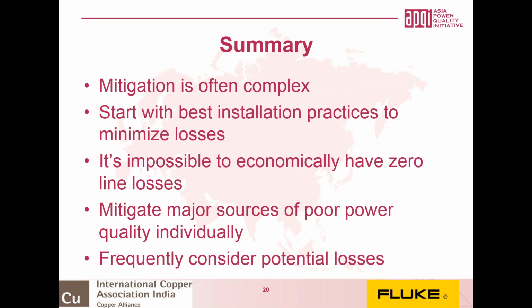Last things are, mitigation is often complex, and first of all, you're best starting with best installation practices to minimize losses. If you size your conductors correctly and you balance your loads properly, then you have a much stronger opportunity to come up with an efficient electrical system. It's impossible to have zero line losses. You have to accept that there will always be some line losses. But one of the things is you should be looking at mitigating the major sources. It may well be that you have to do a Pareto of which are the significant contributors to energy efficiency losses and which ones can maybe be left in place.